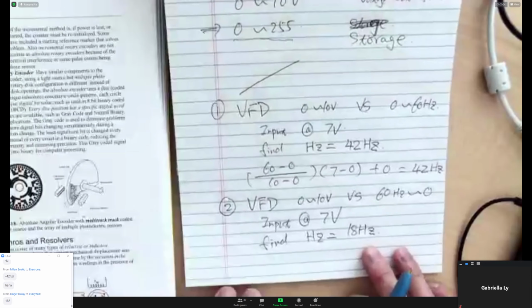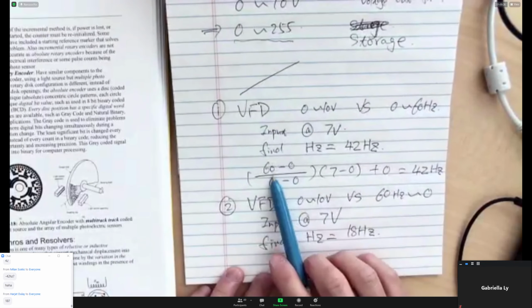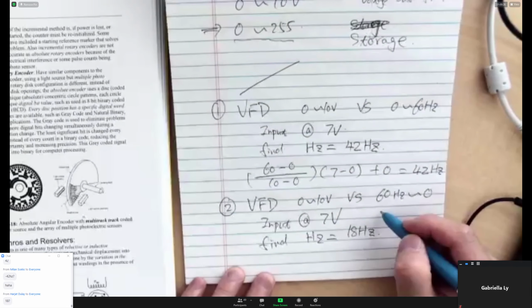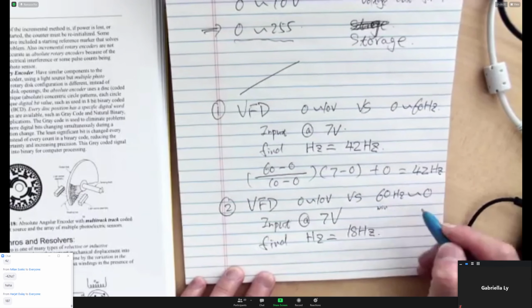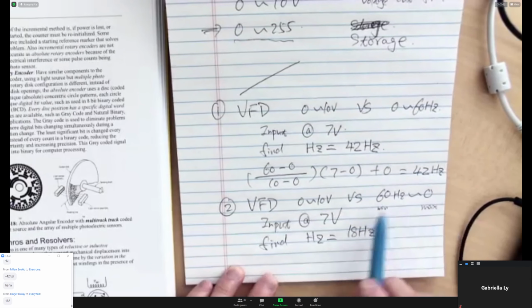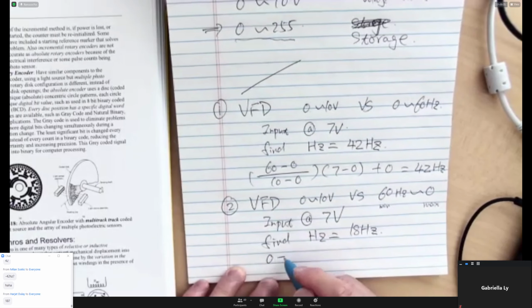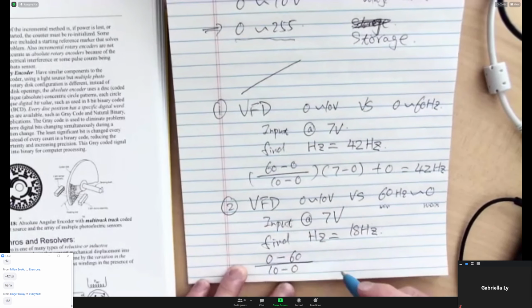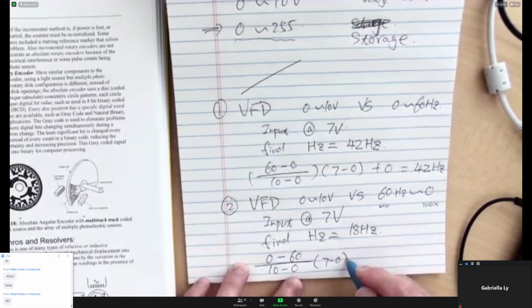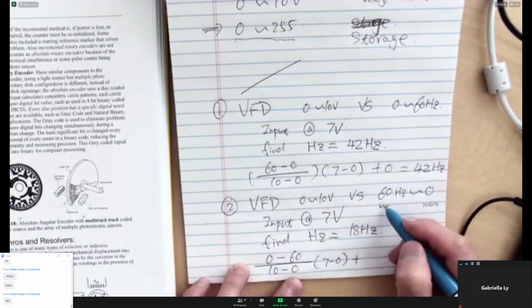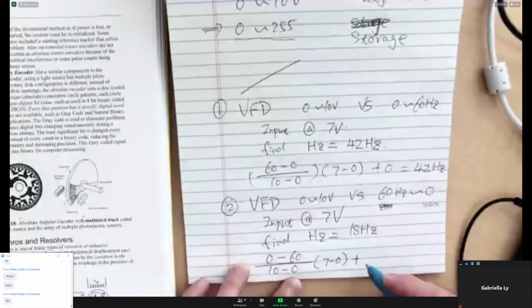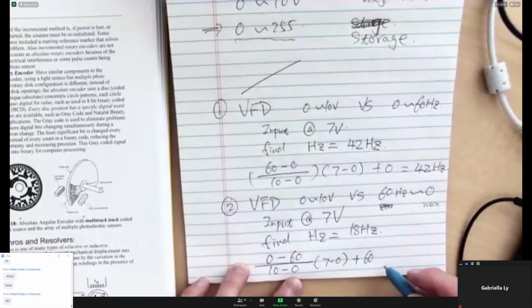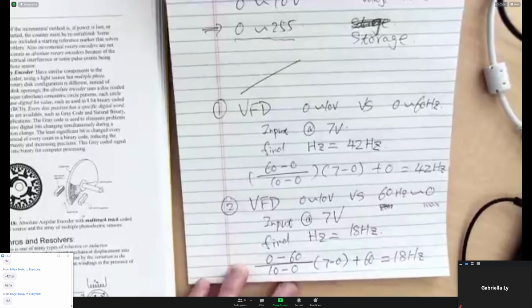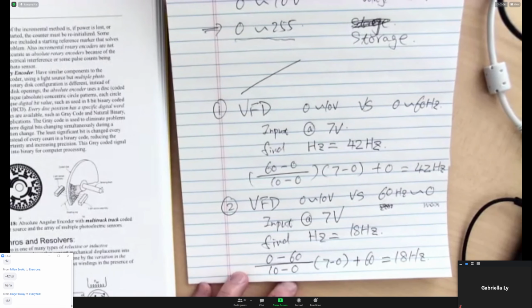So there are two ways we can figure this out. If we put it in the formula, we consider this the minimum and maximum value, and put it the same way: 0 subtract 60, over 10 subtract 0, times 7 subtract 0, plus 60, since that's now our base value. That gives us 18 hertz. Make sense?